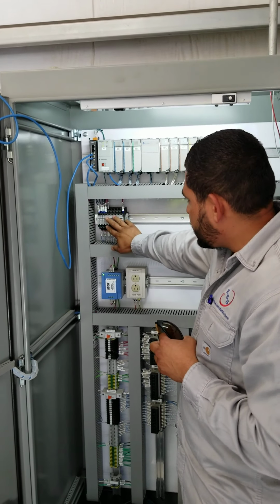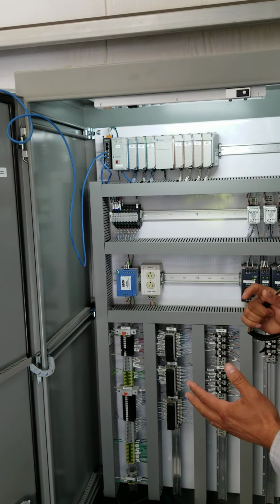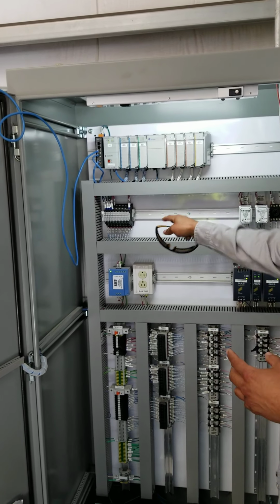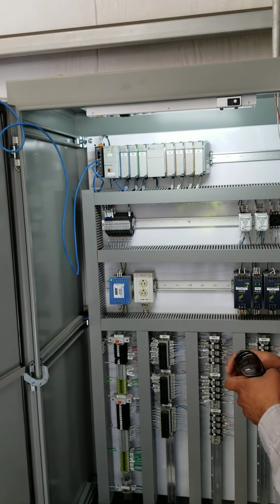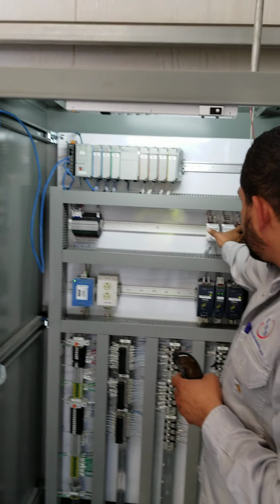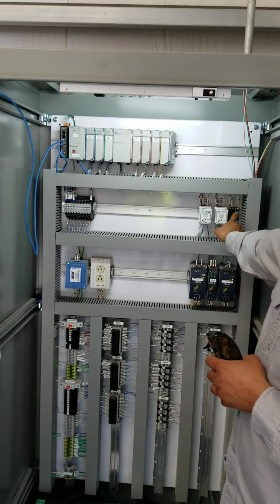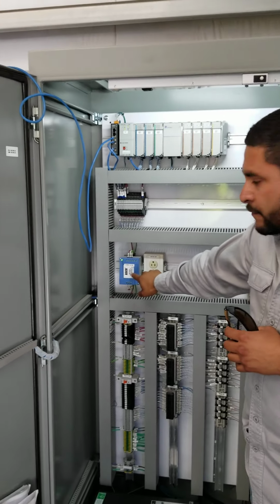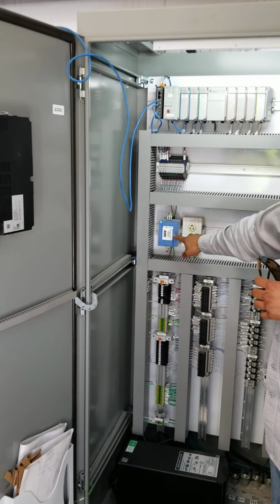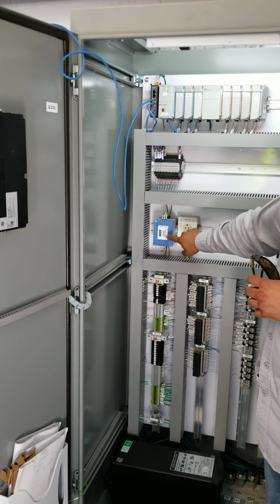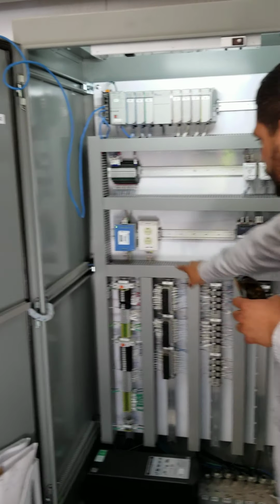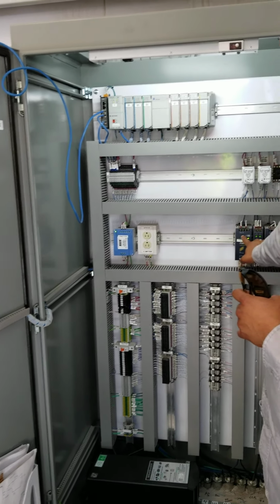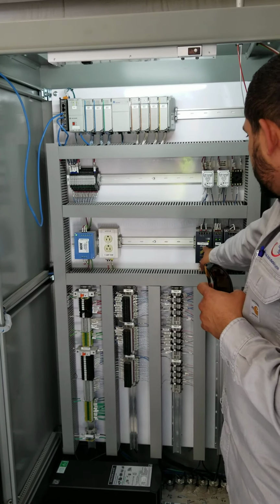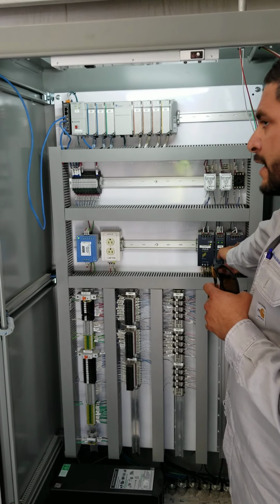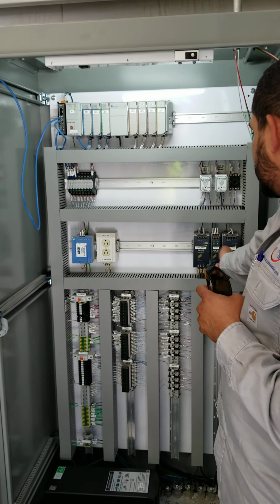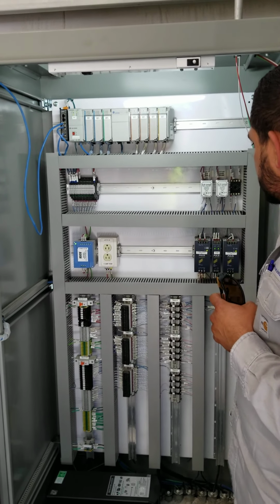We have our relays. That's the outputs for valves, pump starts, the beacon light, the cylinder valve that we have to add air. This section is your probes. This is your probe relays. We have a surge protection for 120. This is a filter for dirty power, so it has to go through here before it goes to my system. Receptacle for laptop use only. We have power supply redundant, so if this fails, it will trigger to the second backup, or vice versa, back and forth, depending on which is primary.